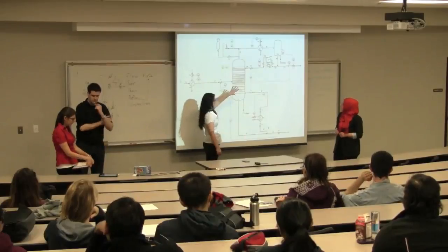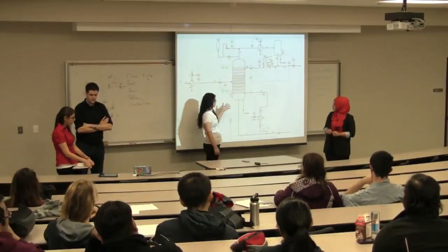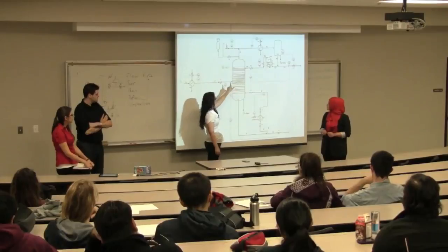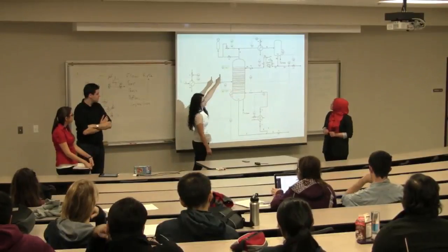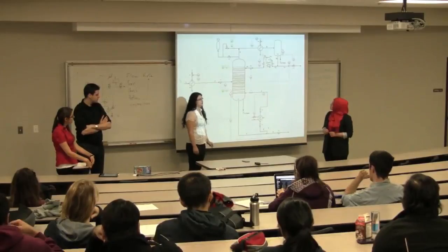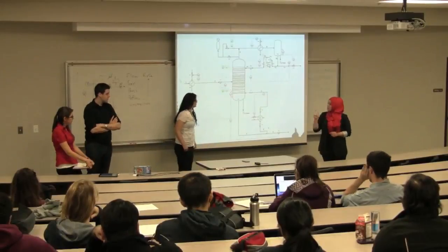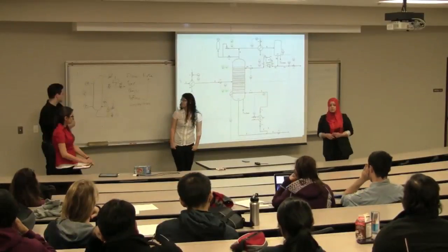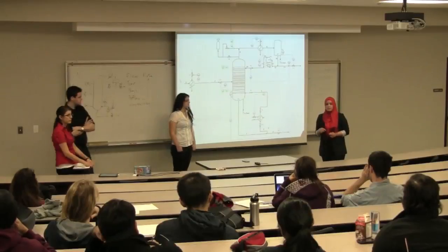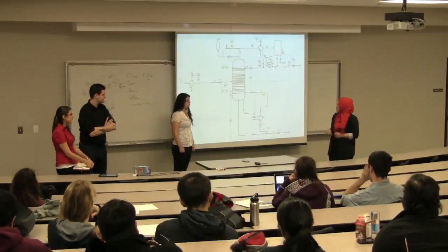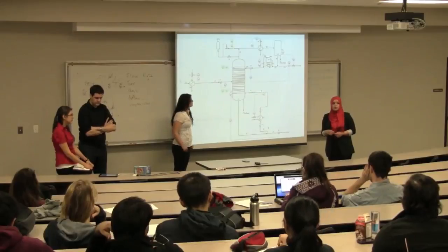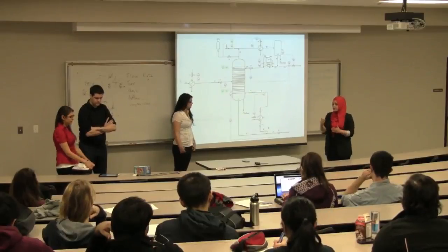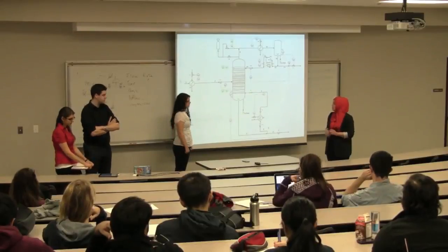Pressure is also a huge thing to be controlled. So we have a pressure indicator on our pump going back in, as well as at the top where the first diaphragm gets set off, so they know to replace it. We had originally added a temperature sensor to each tray, but we actually added a pressure sensor for each tray because it's more important than the temperature in this case. The information gets sent back to the control room where the operator can see the delta P and make a decision based on that.